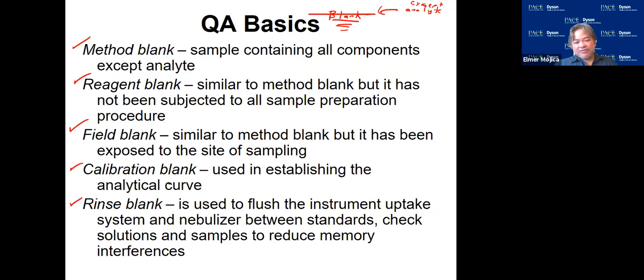So the idea that you have with the calibration blank is you want it to be 0 reading. If not, it might have a reading, and what you do, the reading from that calibration blank, you're going to subtract from the reading of all samples.